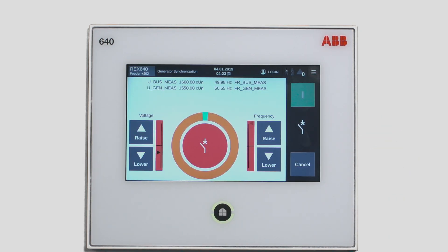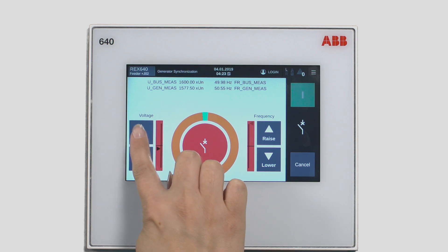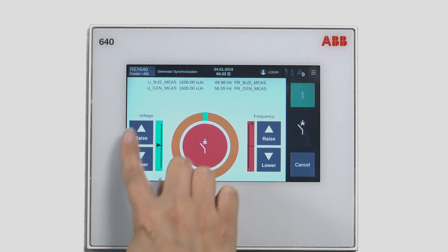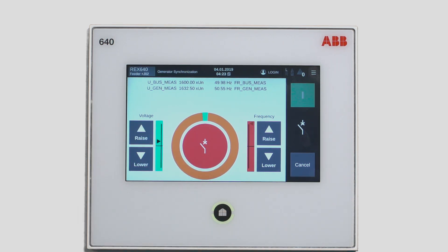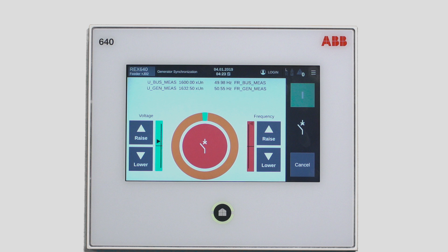Now you have entered the synchroscope view. From this view, you can detect that the voltage of the generator is too low. Increase it up a bit, and the green bar color will indicate that you are within the set limits.